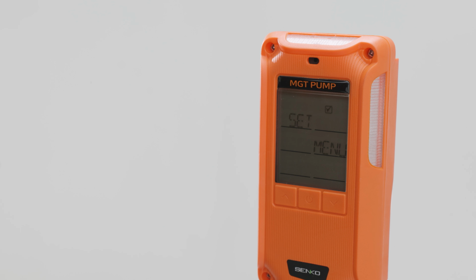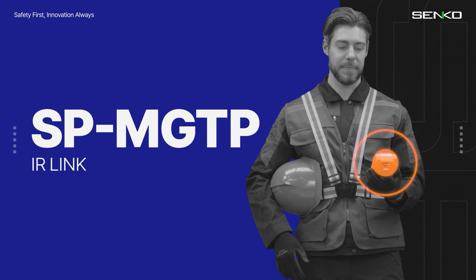By default, the VOC sensor is designed to target isobutylene, and the LEL sensor is designed to target methane, CH4. Finally, there is the init set function, which restores all settings to factory default values. As the name suggests, this menu resets the device to the original configuration set at the factory.